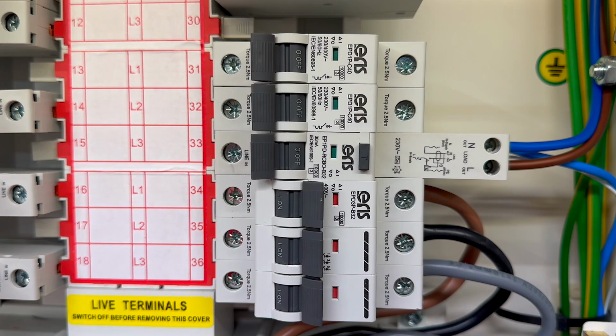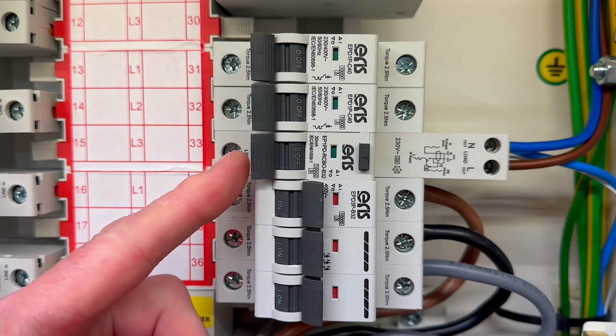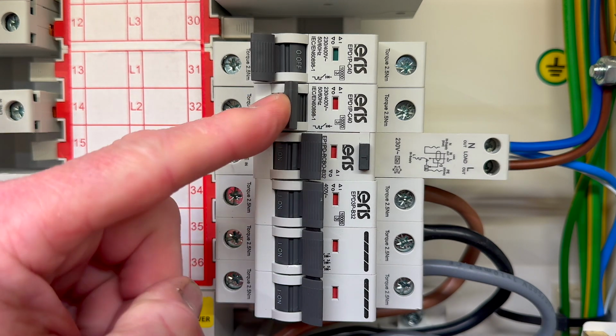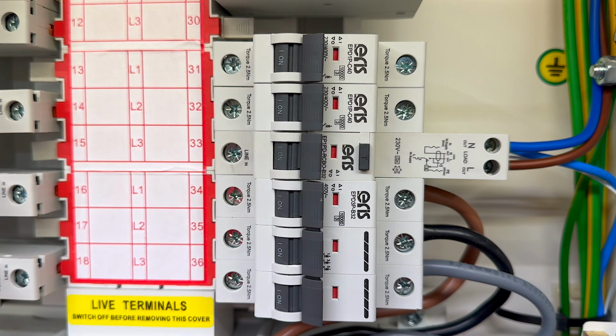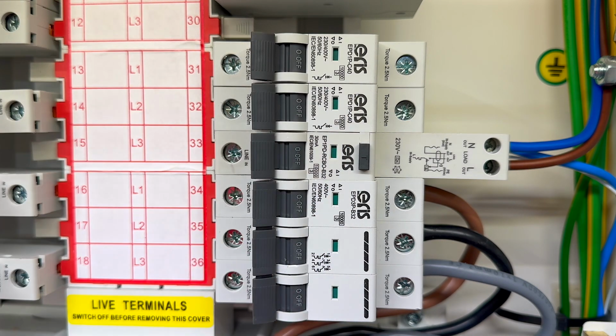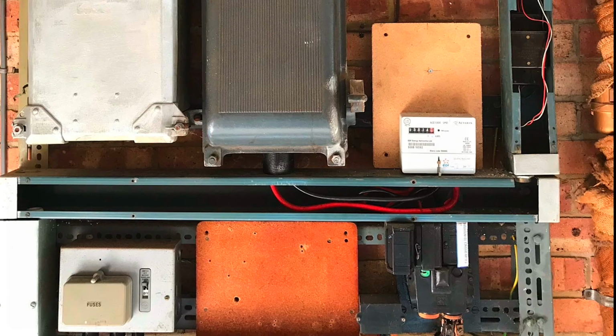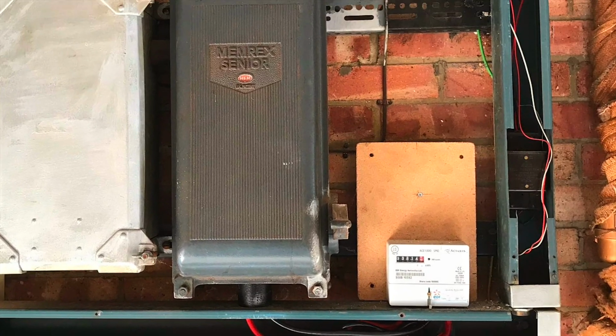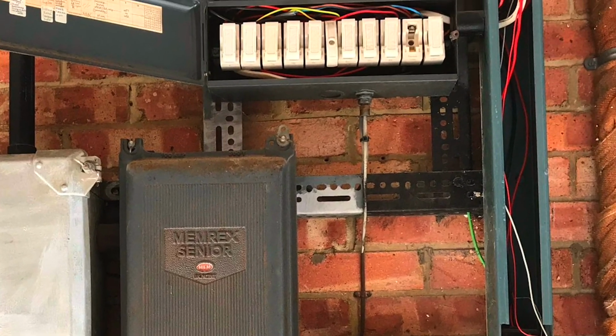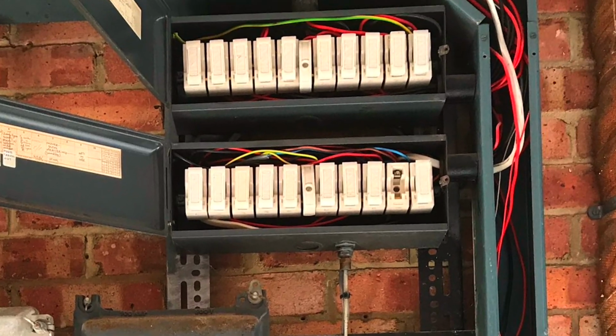Triple pole devices are essentially 3 single pole devices mechanically linked together. This design ensures that all line conductors are disconnected simultaneously if one phase in a 3-phase circuit is overloaded or develops a fault. In the past, when fuses were commonly used for circuit protection, losing one phase of a 3-phase supply was a common fault condition.